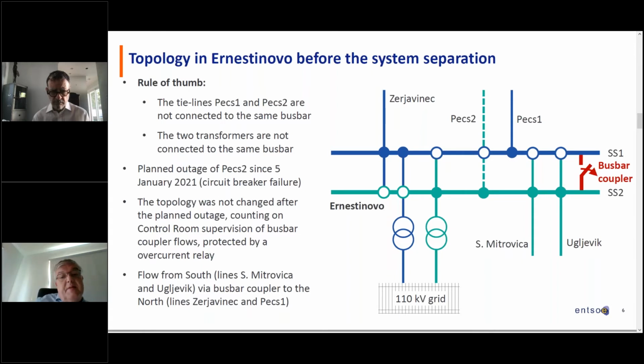The topology then, maybe focused on Ernestinovo. So we have a substation in Croatia, which in normal operation has two lines connected to one busbar, and two other lines, Mitrovica and Ugljevik, connected to the other busbar. And you have Pecs1 and Žerjavinec, which are connected to the first busbar. This is a normal operational situation, but unfortunately, at the time of the split, the maximum power went into the substation from the two lines on the right and went out of the substation from the two lines on the left. So this means that the importing lines into the substation were on one busbar, and the outgoing lines were on the other busbar.